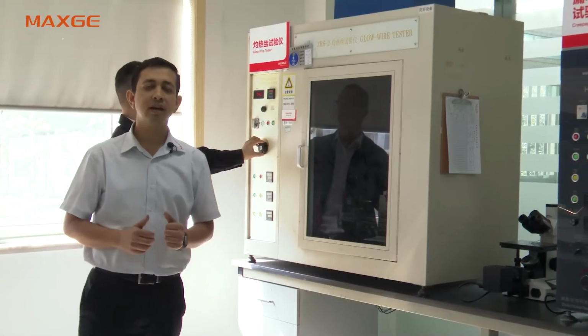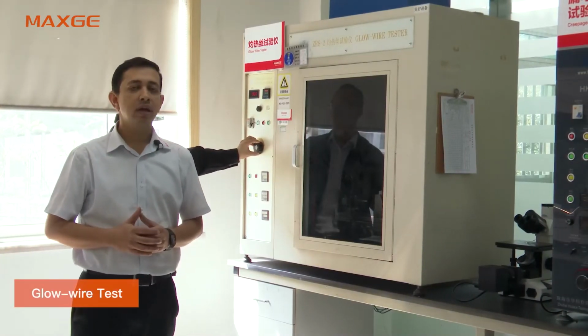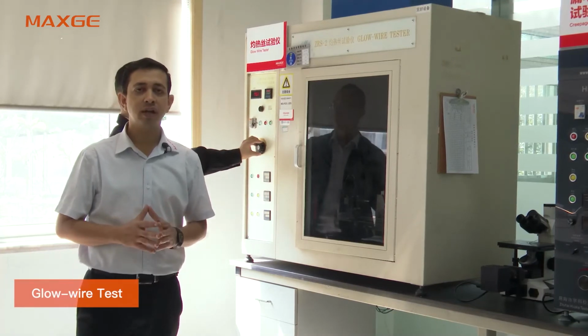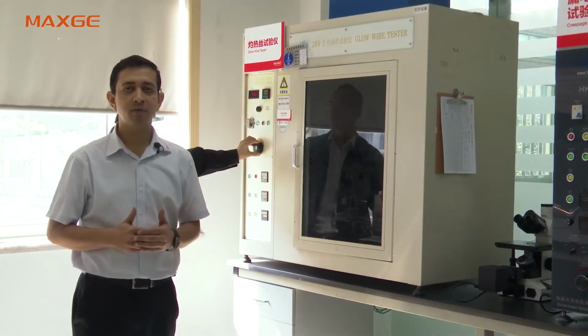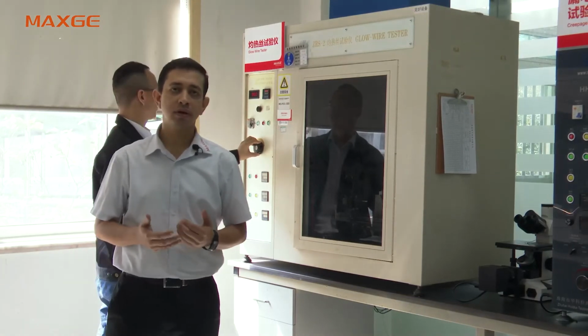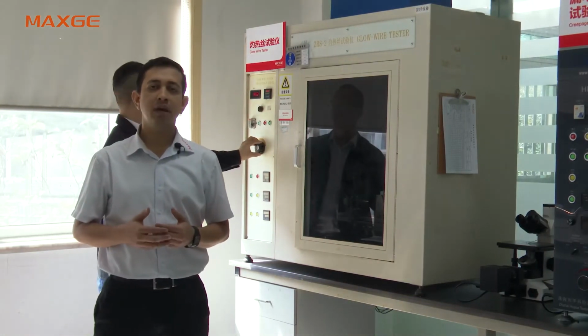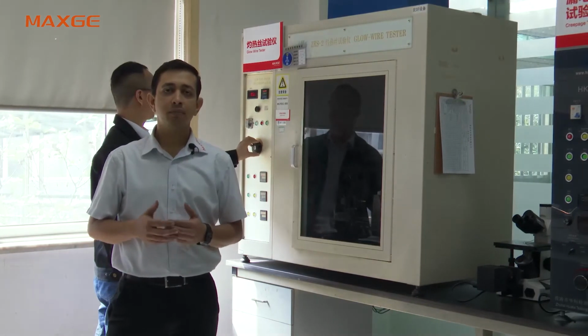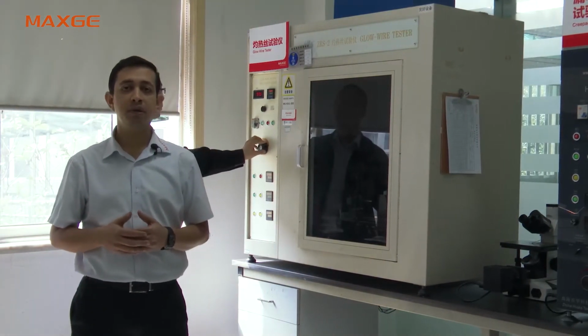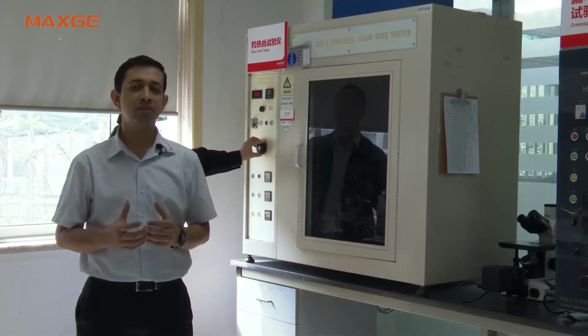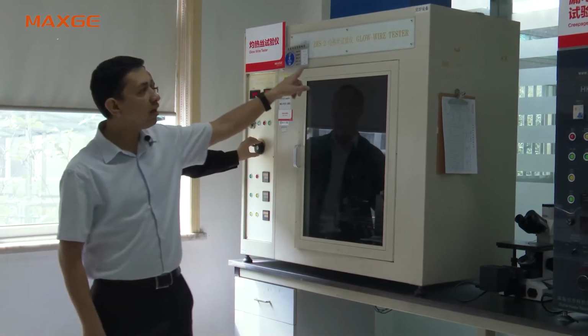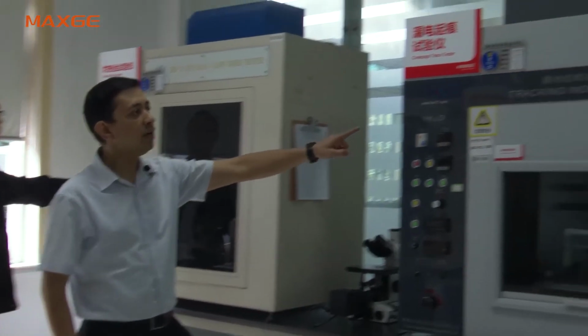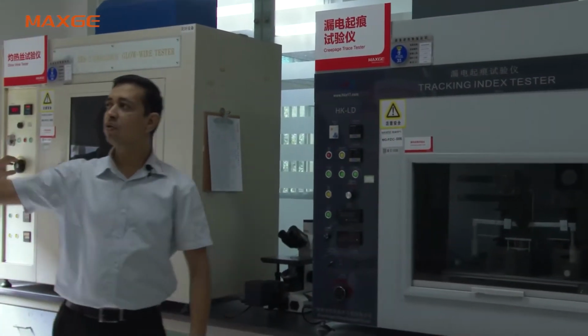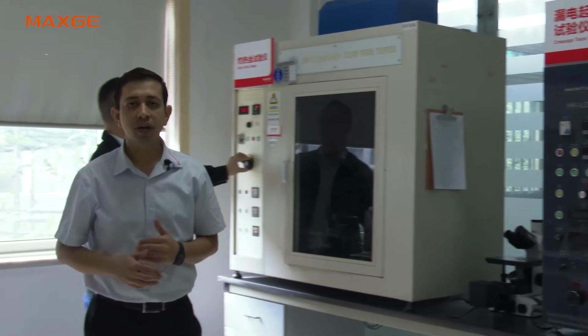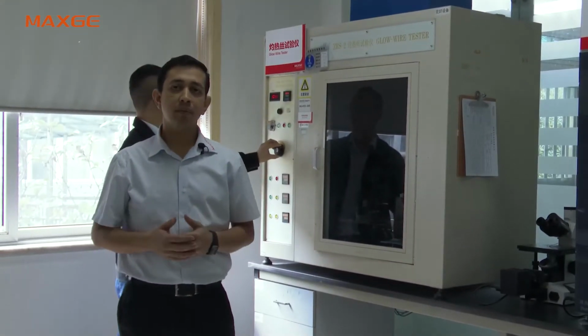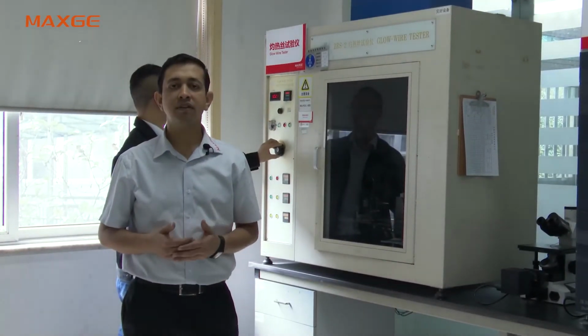Now we are standing inside the plastic testing laboratory. We have this sophisticated laboratory to check all kinds of plastic. We are using the engineering plastic for the MCB and MCCB, RCCB, like polyamides, then PBT, PPS. So all kinds of plastic have to be tested, basically with the glow wire tester, the tracking index tester, and there is also a needle flame tester. These three tests are very important as far as the plastic performance is concerned.